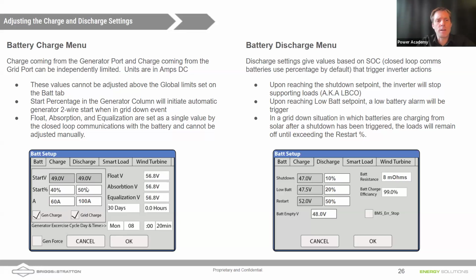What does the start percentage there mean, Daniel? If I've got the generator box checked and I have a generator on the gen port, what does this 40% do for me? That's the percent state of charge of the battery at which the generator would start. Yes, that will initiate a charge cycle. So if you're running off the battery because the grid has gone down, it'll discharge the battery until the battery reaches 40%. Once it gets below 40%, it would start up the generator, and it would charge the batteries at 60 amps DC, and it would also cover the loads in the house.